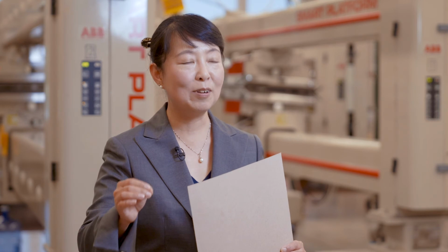The paper maker will have a standard operating procedure for each online sensor they're going to correlate. It's really critical that they follow the standards. The people working in the quality control lab will be working with the paper makers on the machine floor on when to take samples, how to test them in the lab, and how to get data. Based on the results, they have to determine at what point they need to correlate that online sensor, and at what point they need to make a change.